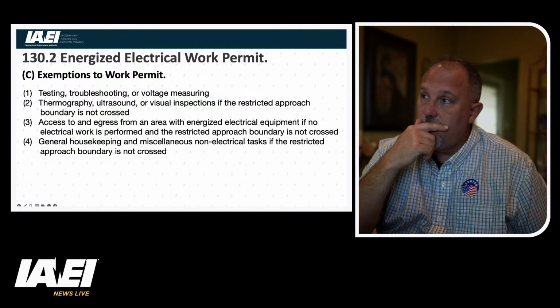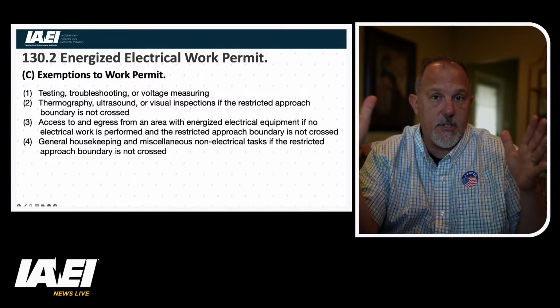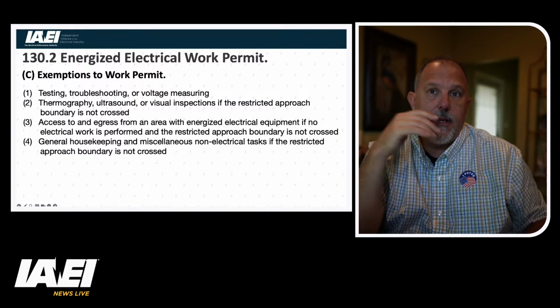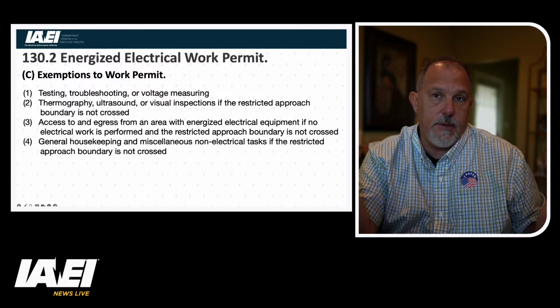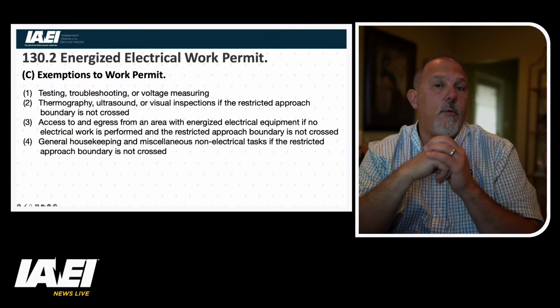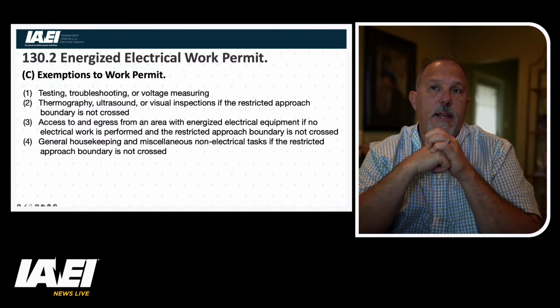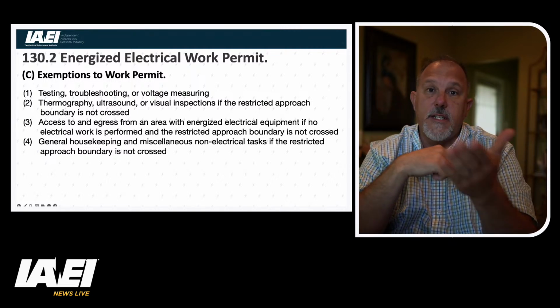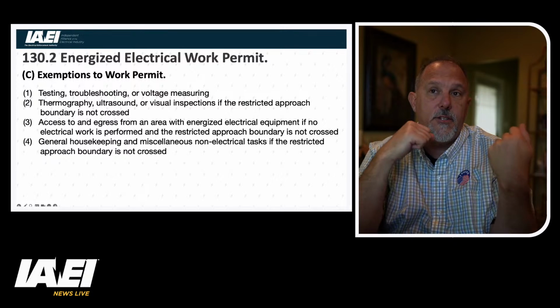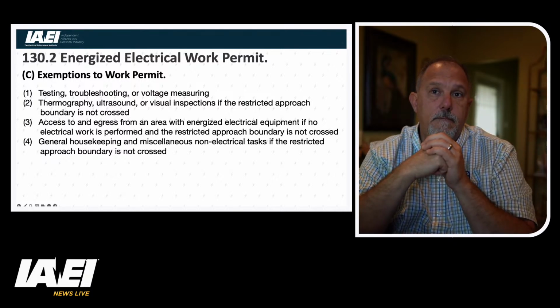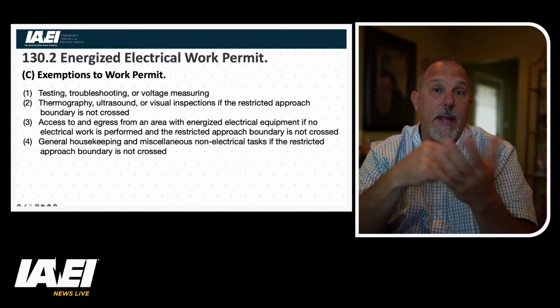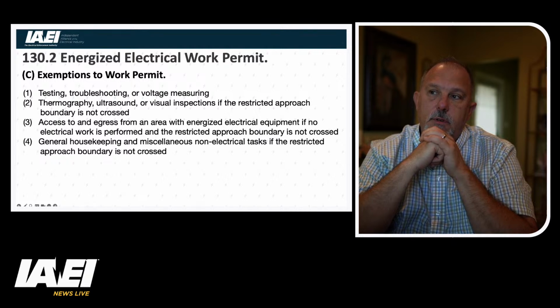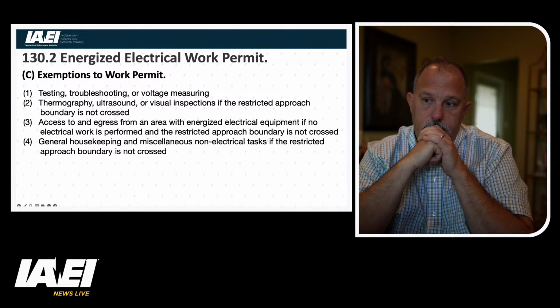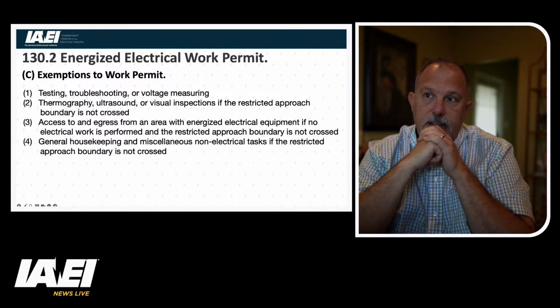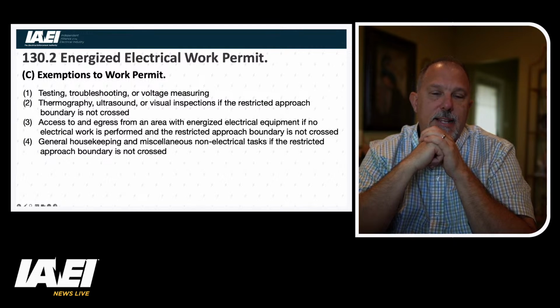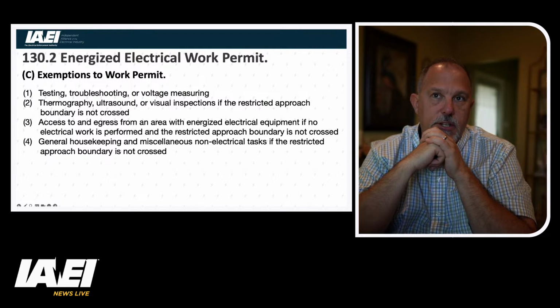I mean, I am exposing electrical parts. What you could say is, once you have exposed electrical parts, you are in an area of energized work. And that's a good example of where the hazards may lie. If I am going to take, say, a panelboard and take the dead front off, or say that safety disconnect switch has a barrier in there, opening that door, I could cause an arc flash event because of poor maintenance on the equipment, etc. But it is possible that I establish an electrically safe work condition, I turn the switch off.